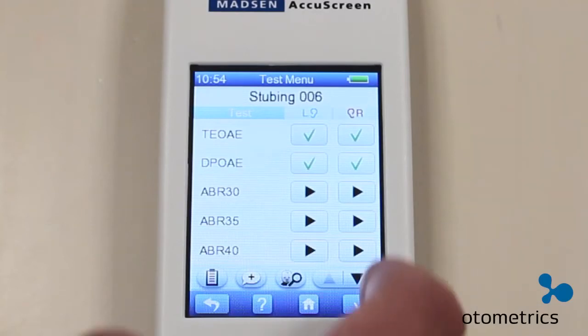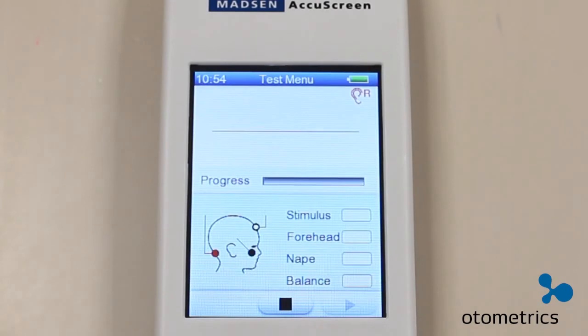When you start the test, Accuscreen will check that the prerequisites for testing are fulfilled. The impedance for the nape as well as for the forehead is measured. This value must be below 12 kiloohms for the test to pass. The balance must be below 4 kiloohms.